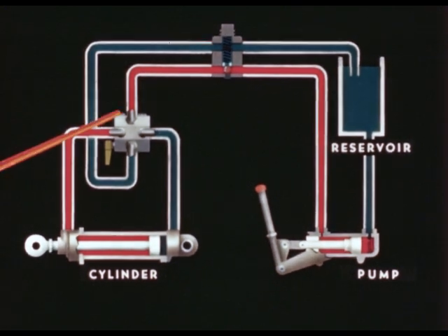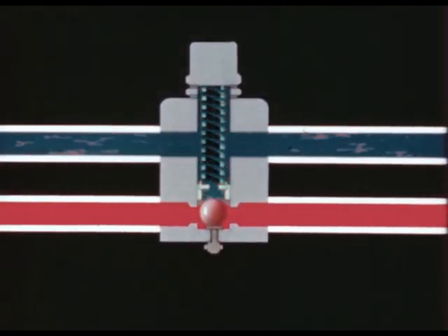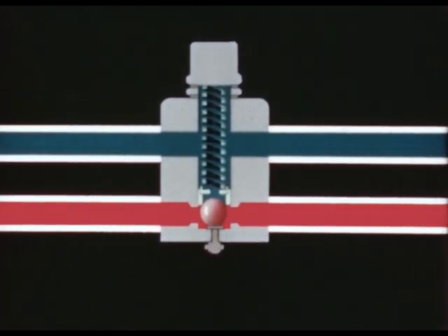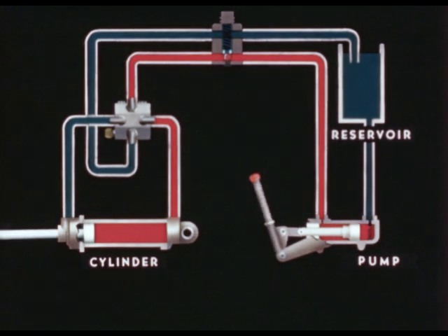A relief valve, usually of the spring-loaded type, is installed between the pressure line from the pump and the return line to the reservoir to permit continuous operation of the pump. This valve permits the return of the fluid to the reservoir.